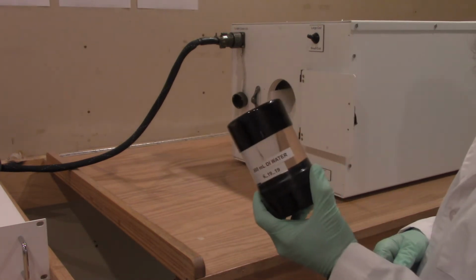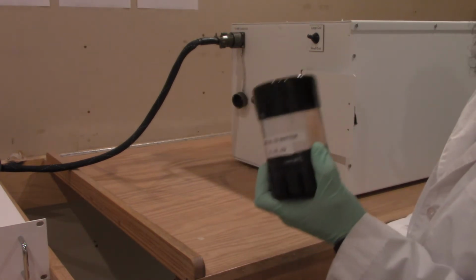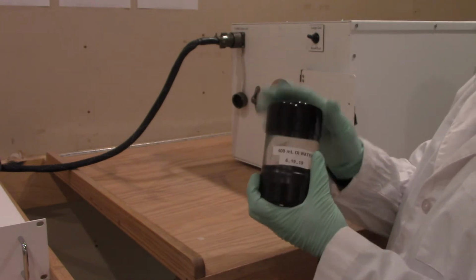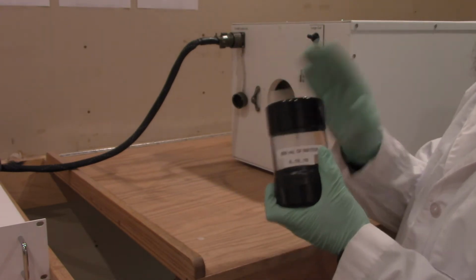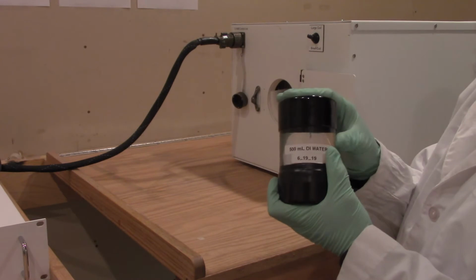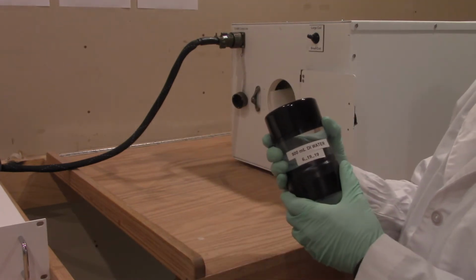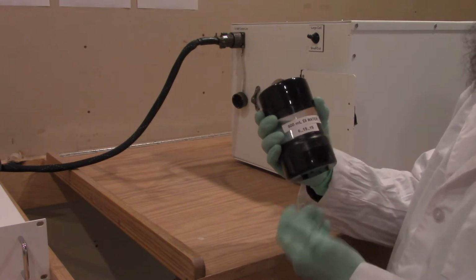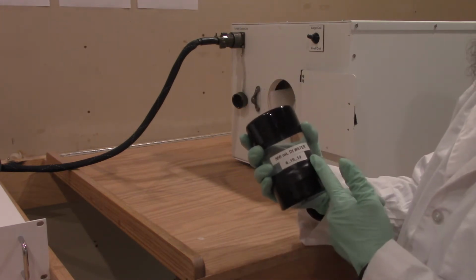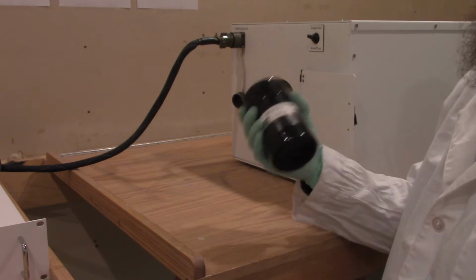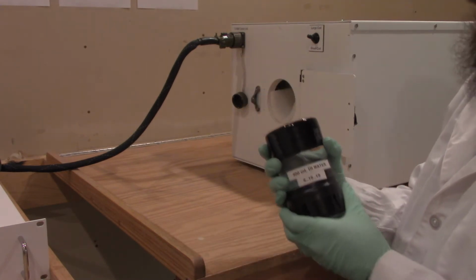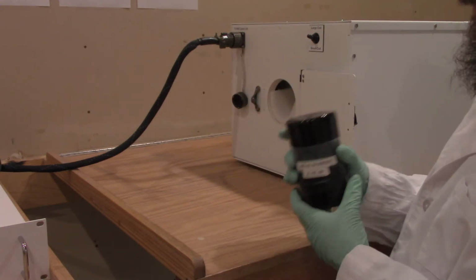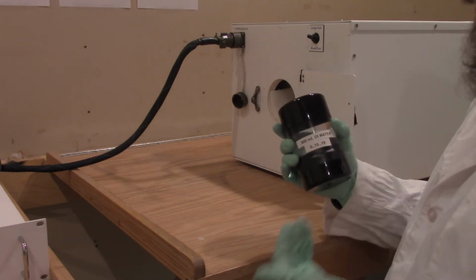So we'll start with our calibration blank. We'll put that in the instrument. There are a couple of things that we need to consider. Number one, we need to have these samples at the same temperature as the instrument. So if you're going to fill your blank or make your samples, you need to leave them for a few hours to let them equilibrate to the temperature of the lab.